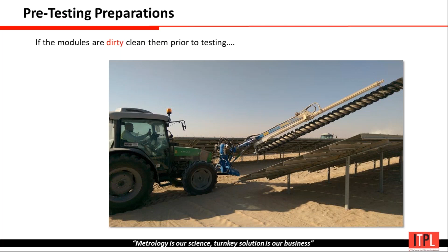And if your P max at real time condition is on the lower side, that will clearly impact your STC values also. In that case, we won't be able to justify the values we are getting at STC, and whatever the module manufacturer is saying, we can't justify those values. So we have to make sure to clean the solar panel before starting the testing. This is the most important part.